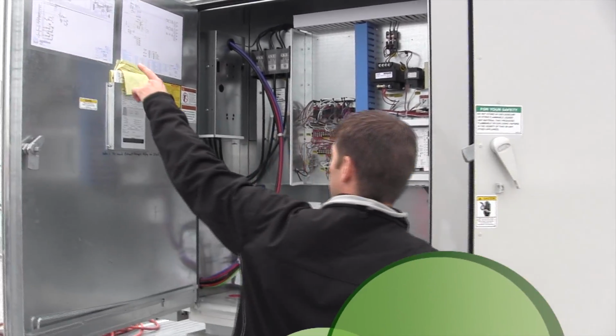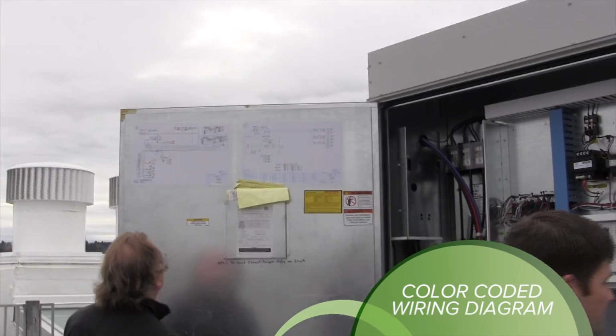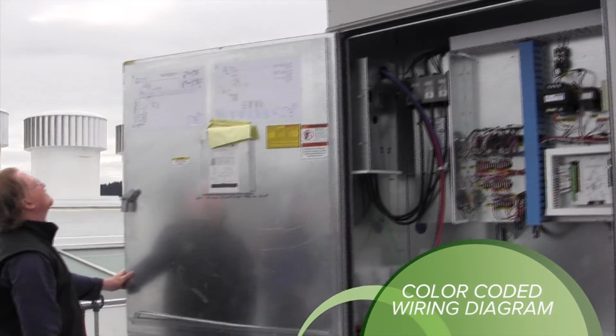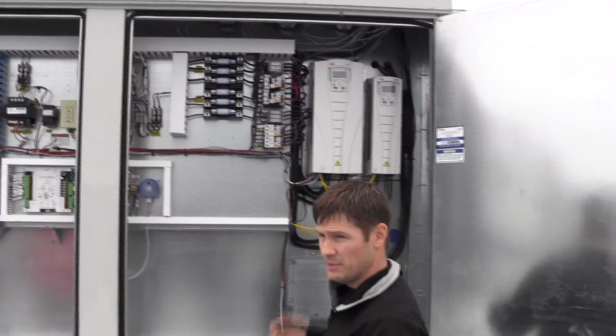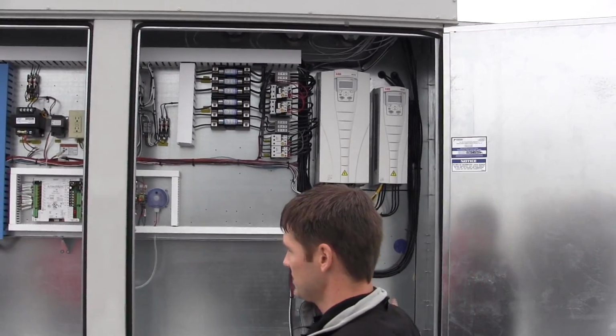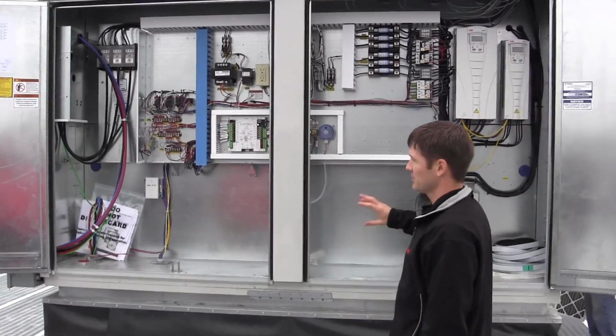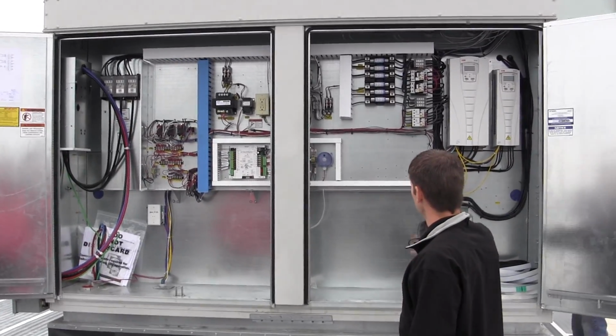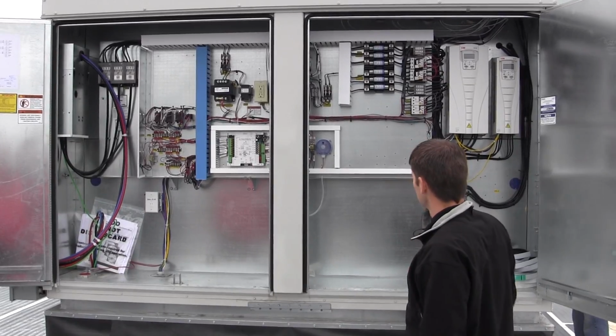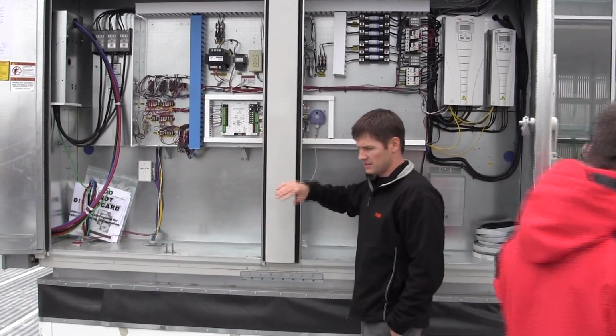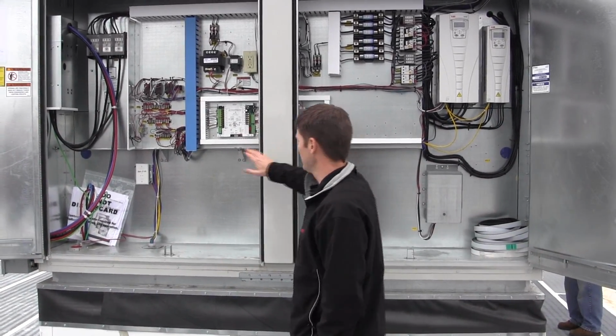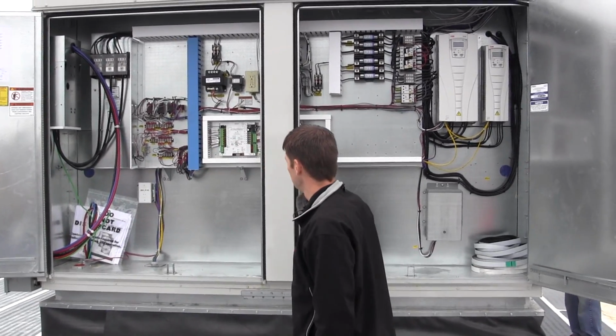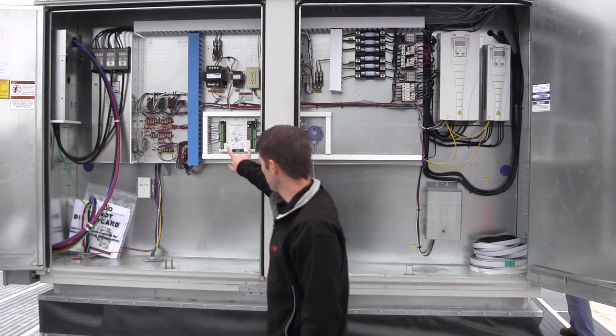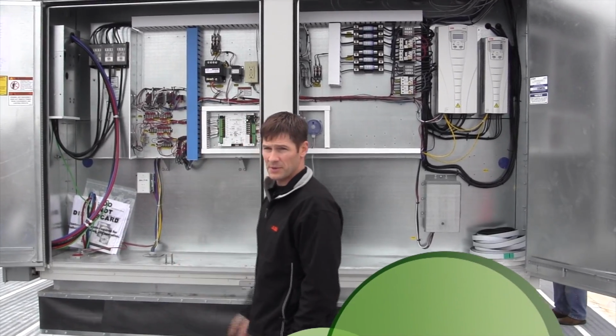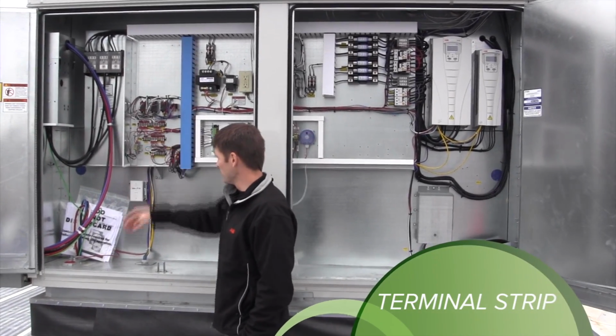Here's your laminated, color-coded control wiring diagrams. Your ABB VFDs, we have a separate training session for ABB. But you can see there's tons of room in here, and that's because you don't have gas heat or electric heat, and you don't have compressors. It's just very simple. You've got all your contactors. There will be isolation relays that Automated Logic will be installing. Right now, they're controlling everything directly. This is that long terminal strip I was talking about. This is where you can control everything in the unit.